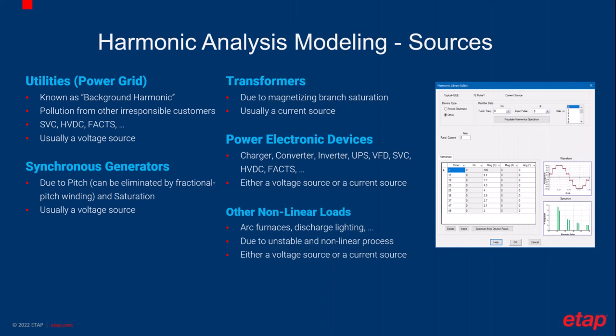Here's a list of common harmonic sources. In general, they can be categorized as voltage sources and current sources. Usually, the power grid is considered a voltage source. Synchronous generators and transformers, under certain conditions, generate harmonic voltage or current. Power electronic devices, such as inverters, and other nonlinear loads such as arc furnaces, are very commonly seen as voltage or current sources in the power system. In ETAP, the harmonic sources can be modeled by using the harmonic library or the element editor. Now let's see it in ETAP.